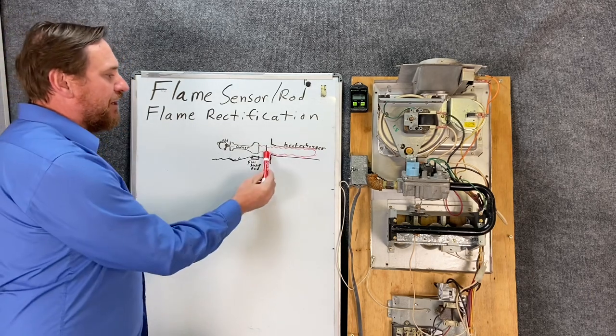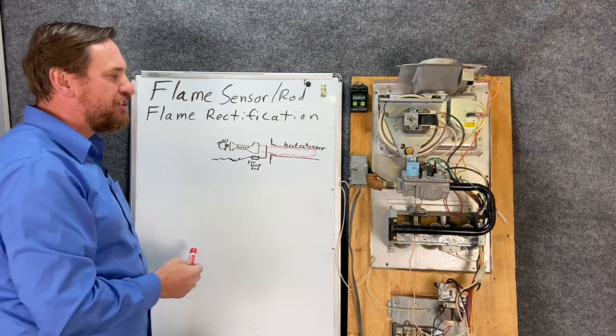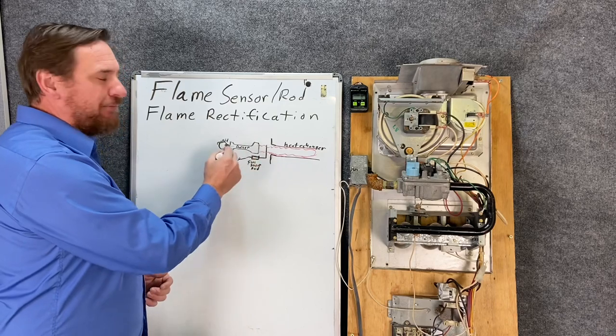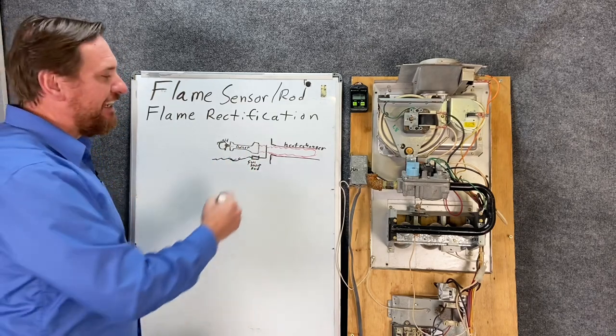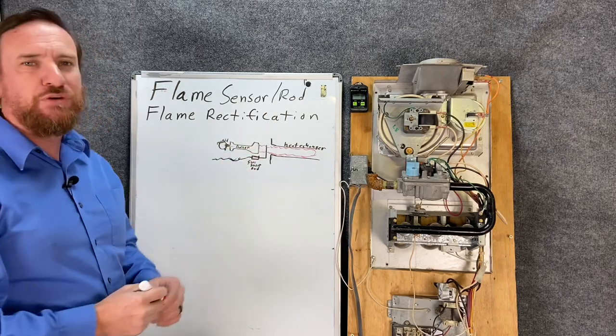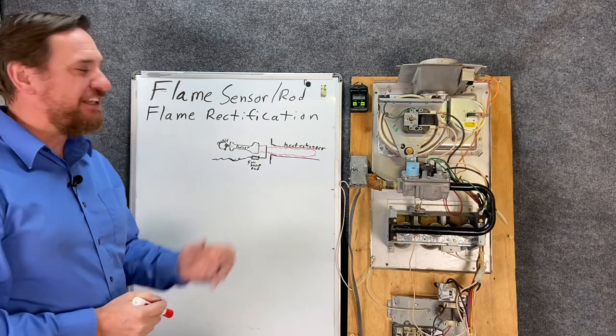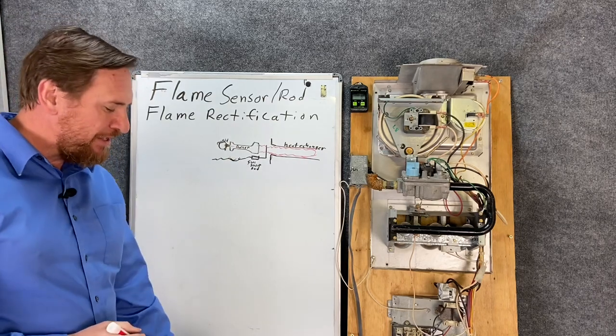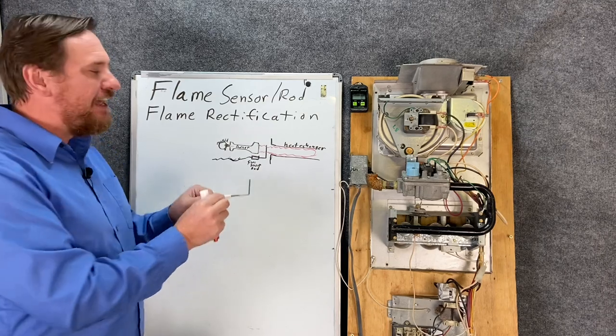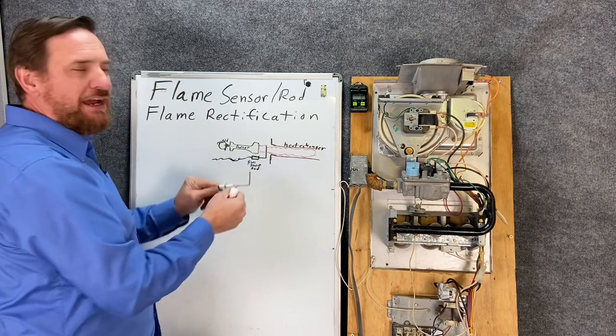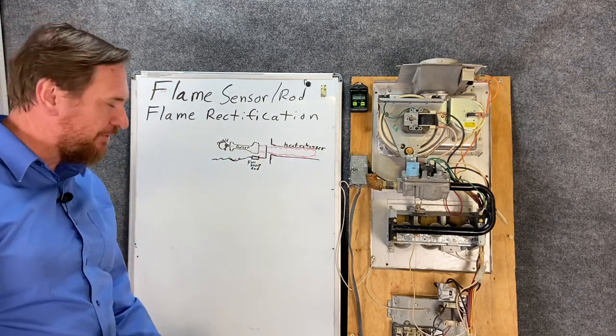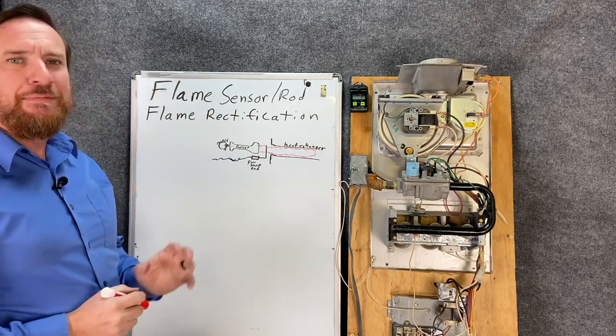The flames conduct electricity, allowing electricity to flow from the flame sensor to the metals. Now some people argue that it's going to the burner side, some people argue that it's grounding out to the heat exchanger side, some people say it's both. I really don't care, as long as the unit is grounded, the burners are grounded, and the control board is grounded, it gets that signal back to the control board. So it's really cool that the flame itself is actually conducting electricity. The flame itself is the switch.